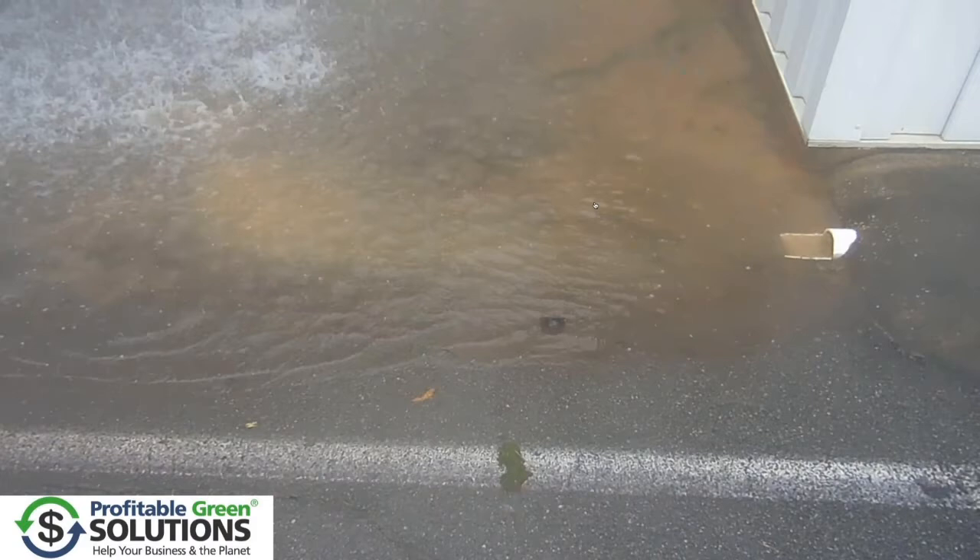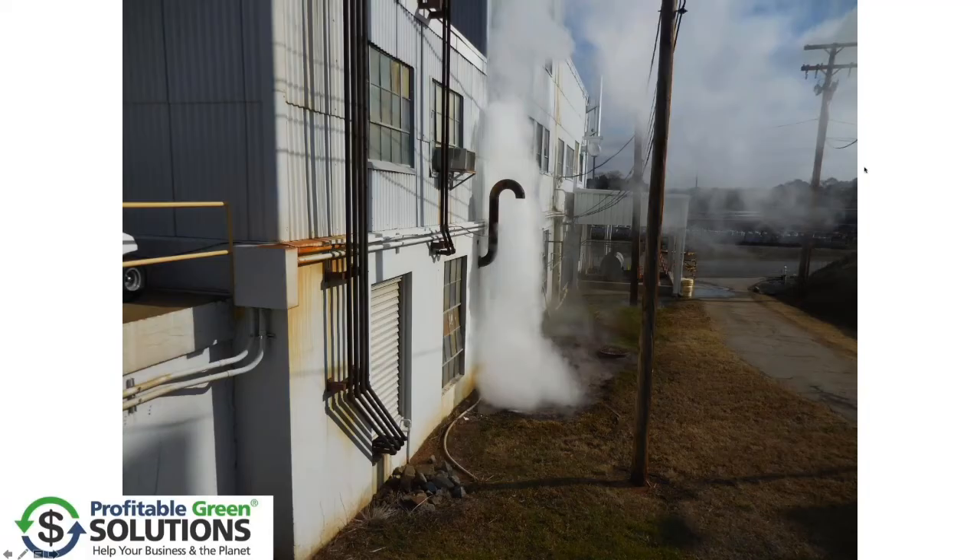So this was a Boiler MACT audit and we just happened to notice this cooling tower — something wrong there — about 150 gallons being thrown away every 10 minutes.